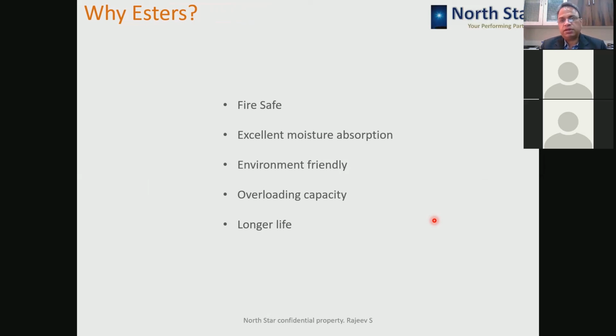So what are esters, and why should we use esters in our transformers in place of mineral oil? Transformers are notorious for catching fire and failing unpredictably. It is a wrong word, saying unpredictably, but the fact is that suddenly a transformer fails, and the failure is so violent that it results in a huge fire, causing big damage to property and life. So oil-filled transformers are considered to be unsafe as far as the safety of people and property is concerned. Many incidents have happened and are happening. The Uphaar tragedy is one such tragedy, where in a cinema hall in Delhi a transformer failed, burst, caught fire, and many people died. After that tragedy, the ruling came that in complexes and crowded places, oil-filled transformers cannot be used, due to the type of transformer.